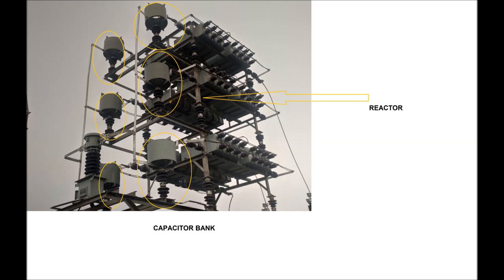In this figure, a capacitor bank operating at 20 MVAR has been shown. There are six reactors. The 20 MVAR capacitor bank is of double star connection for three phase. In each star, in each phase, there exists a reactor in series with the capacitor series-parallel group combination. Therefore six reactors are used.